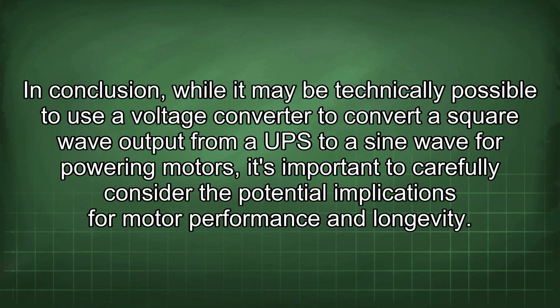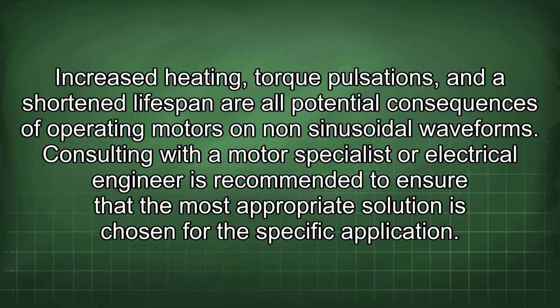In conclusion, while it may be technically possible to use a voltage converter to convert a square wave output from a UPS to a sine wave for powering motors, it's important to carefully consider the potential implications for motor performance and longevity. Increased heating, torque pulsations, and a shortened lifespan are all potential consequences of operating motors on non-sinusoidal waveforms. Consulting with a motor specialist or electrical engineer is recommended to ensure that the most appropriate solution is chosen for the specific application.